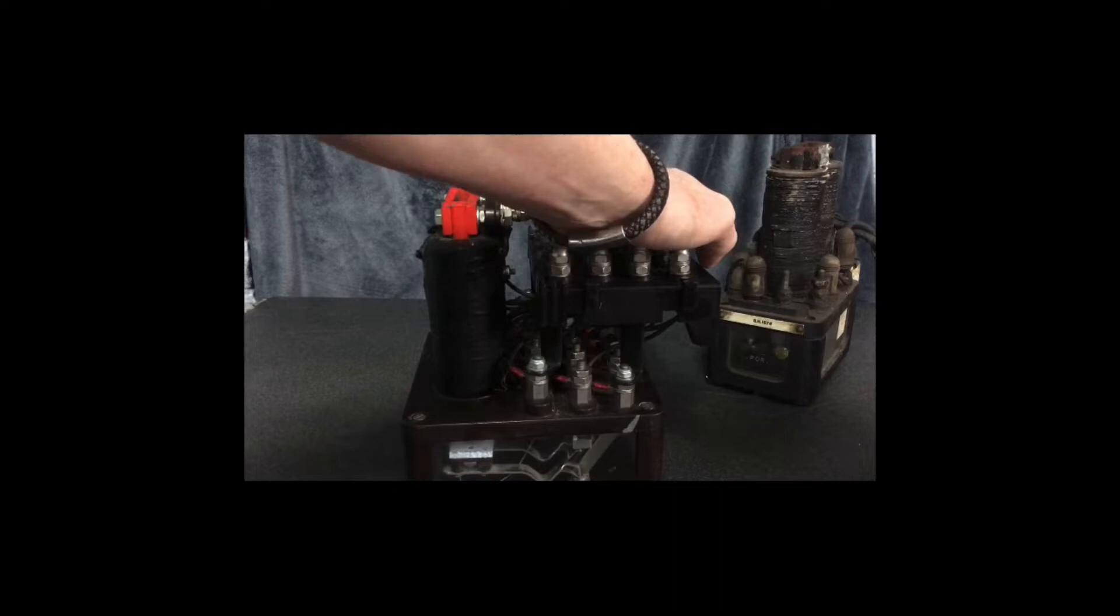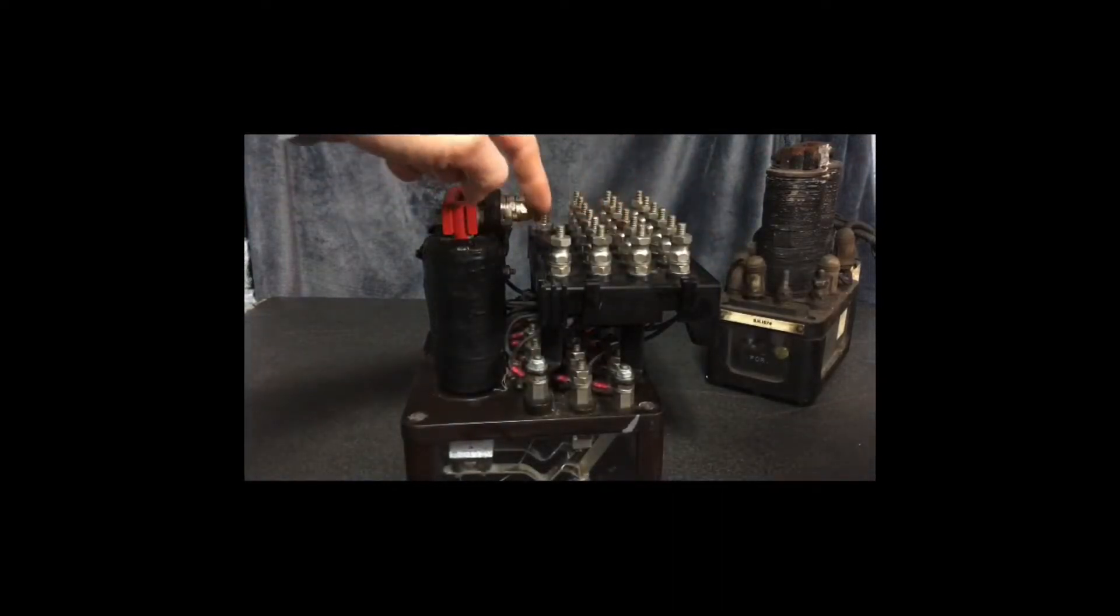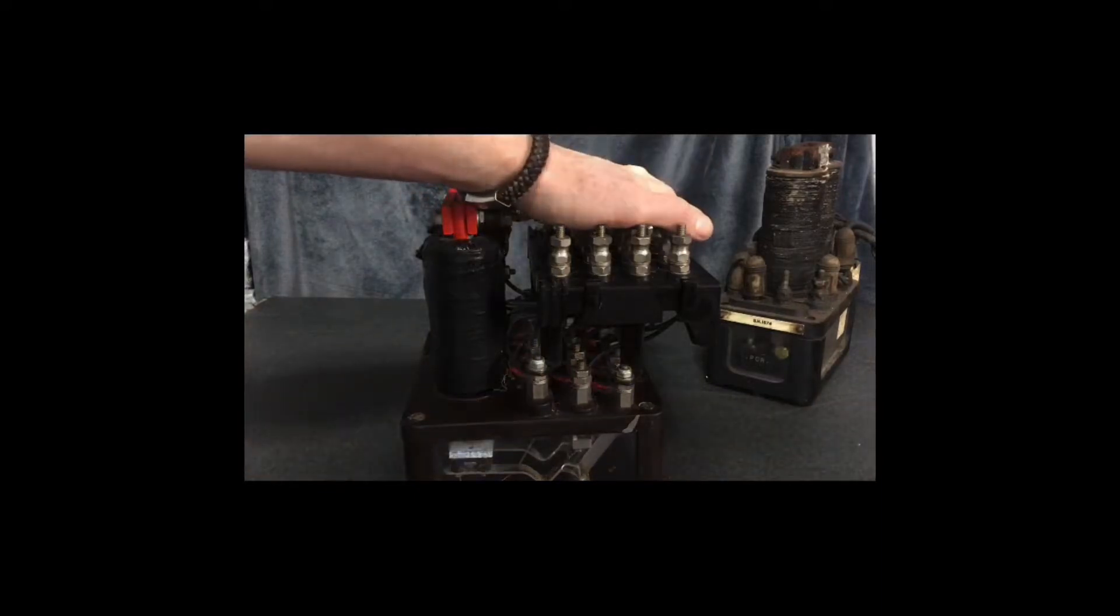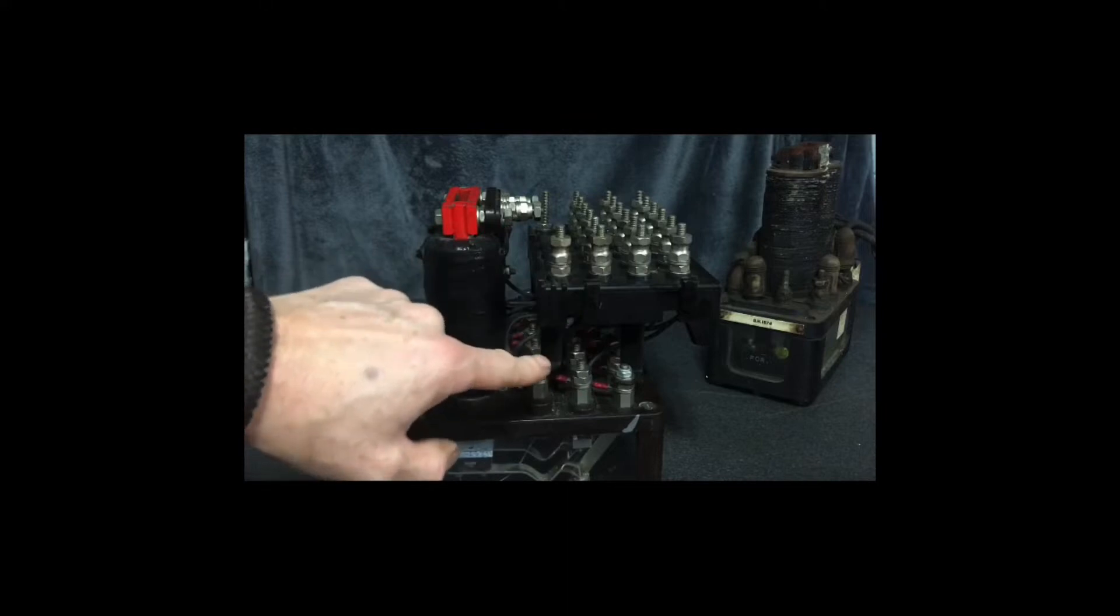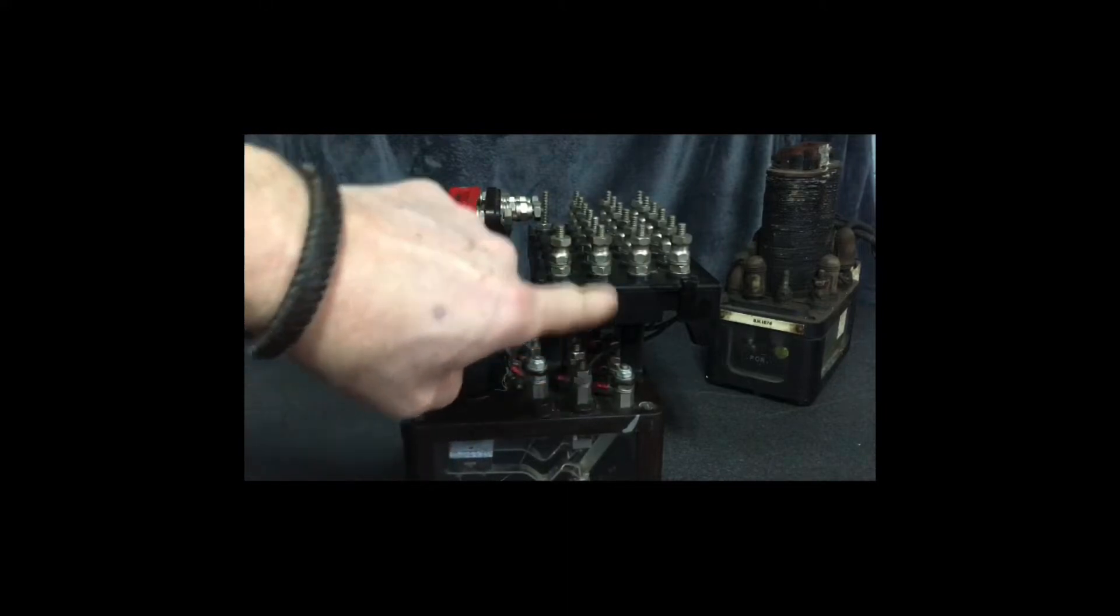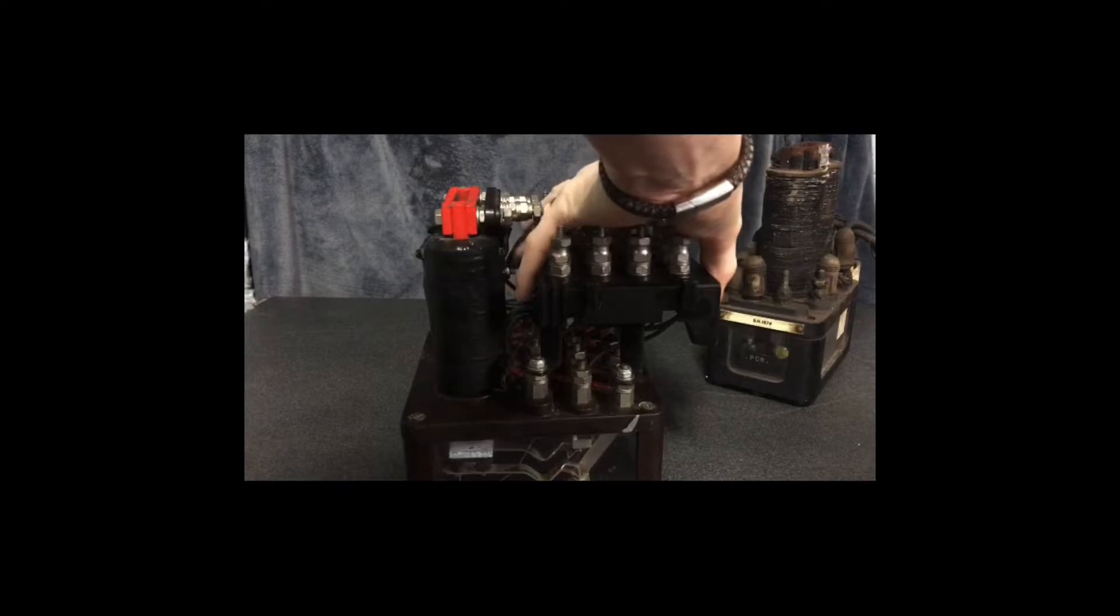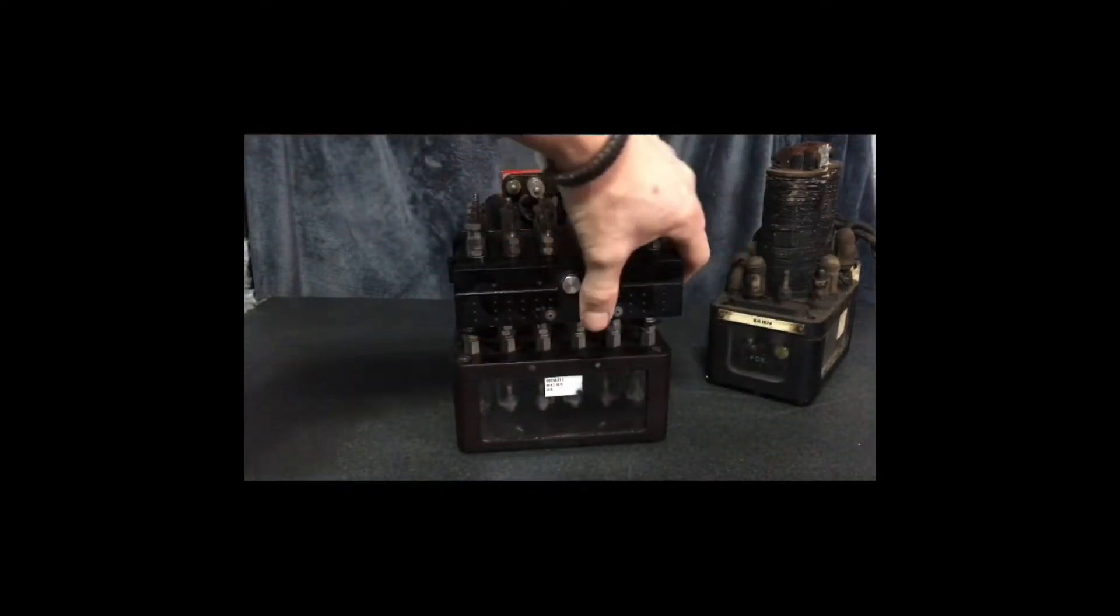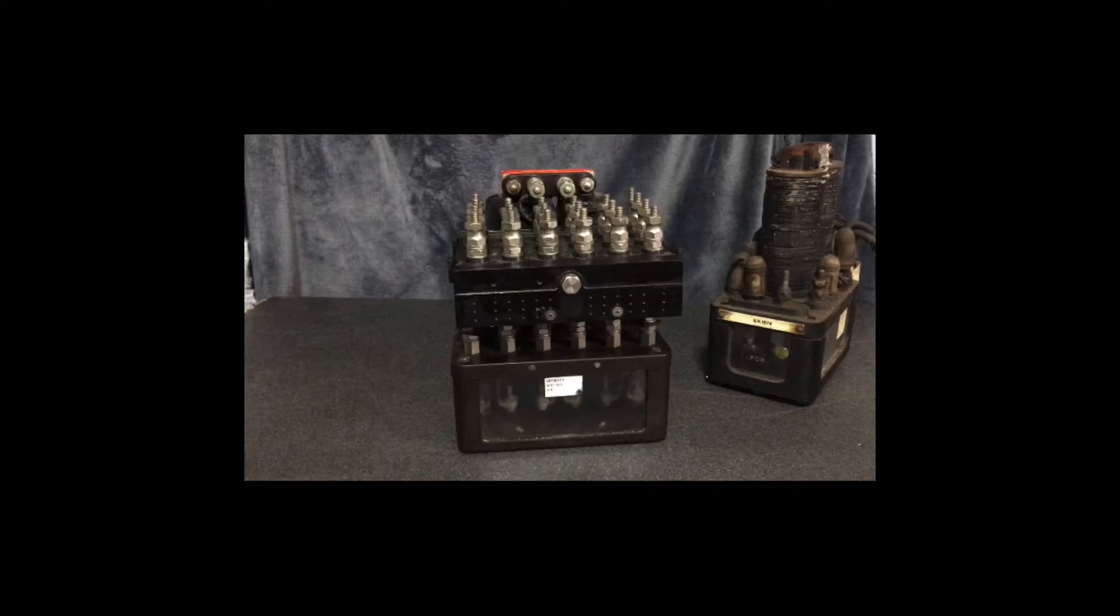You don't have to dewire it then, which makes life a lot easier. It's down to a few minutes changing the relay, but more importantly testing wise, you're not having to remove any wires. So you're not having to do correlation checks to make sure it's all gone back on.